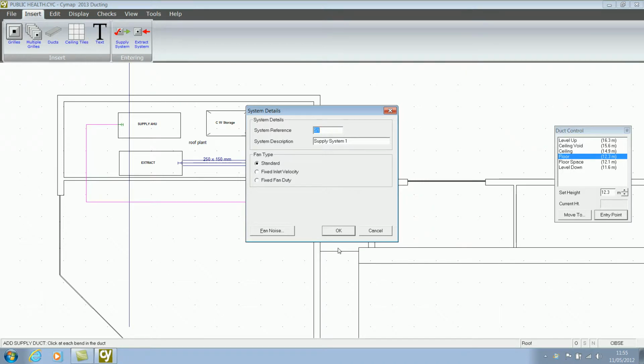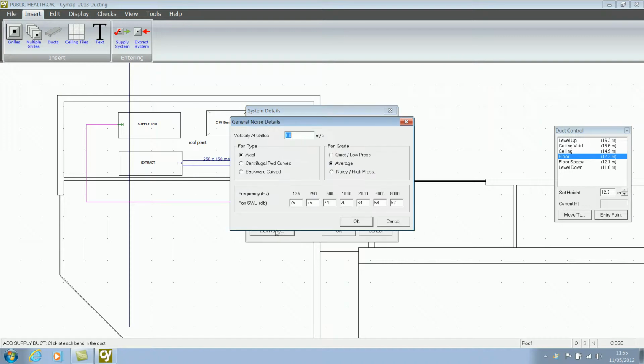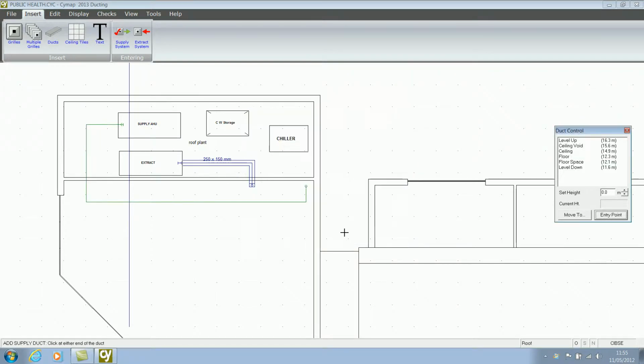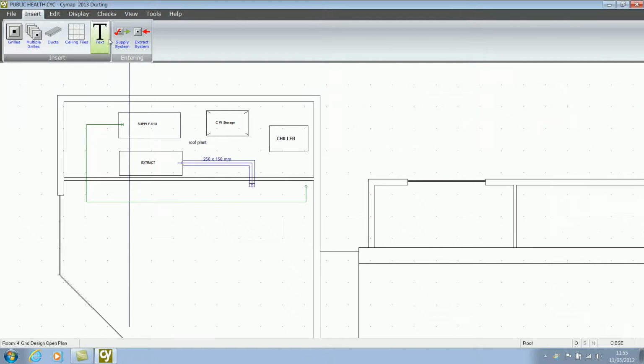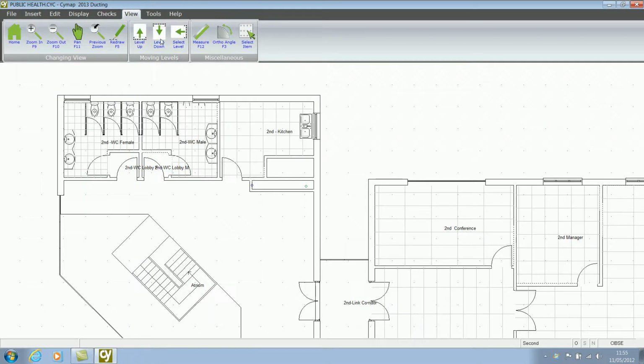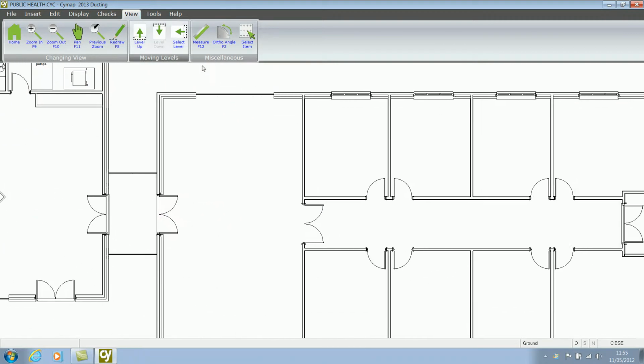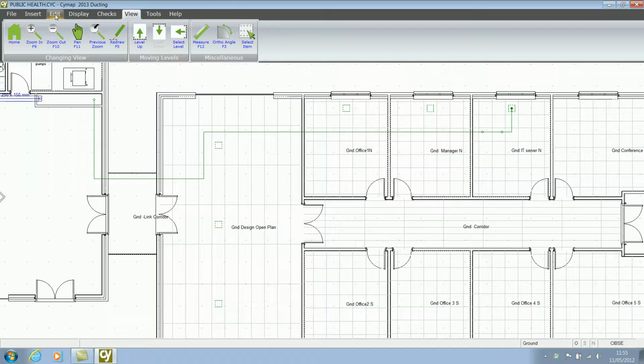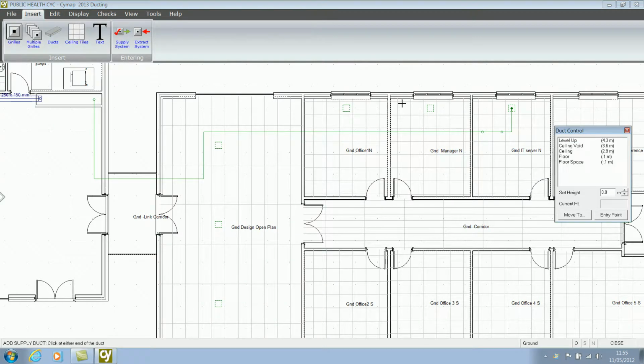Later on, once you've ascertained your system resistances, you can get the fan noise information from a manufacturer, and you can add in your own data to do noise checks within the rooms. Cancel the command, and then we can level down and connect the ductwork into the office areas. Back to the insert ribbon, ducts. I can also go from the bend and connect to the grill, so I can go forward or backwards depending which way I want to go.